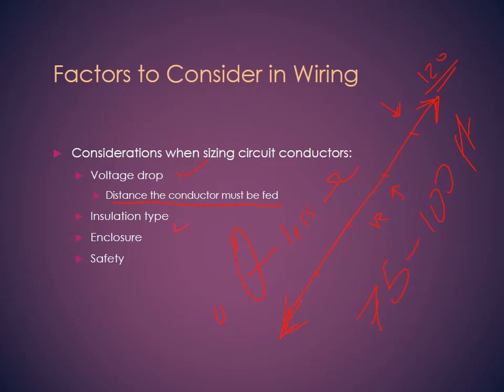We have to care about the insulation type, because we have to know: is this place going to be very hot? Is it going to be exposed? Is it under sunlight? Based on that, we can also know what the enclosure should be. Is it going to be rainy? Is it going to be exposed to some chemicals? Based on that, we can choose the proper enclosure. Again, you don't want any exposed wiring. I know you might see it somewhere, but that's not the code. They should always be enclosed. It's a big safety issue.